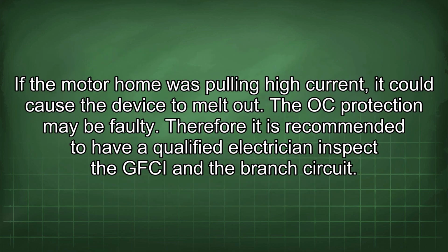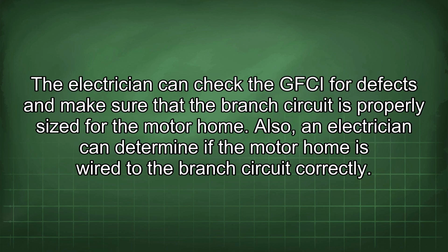If the motorhome was pulling high current, it could cause the device to melt out. The overcurrent protection may be faulty. Therefore, it is recommended to have a qualified electrician inspect the GFCI and the branch circuit. The electrician can check the GFCI for defects and make sure that the branch circuit is properly sized for the motorhome. Also, an electrician can determine if the motorhome is wired to the branch circuit correctly.